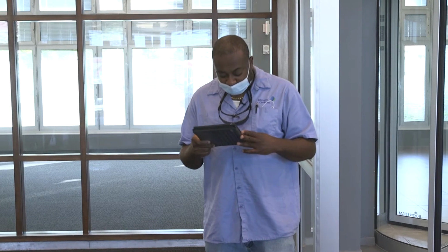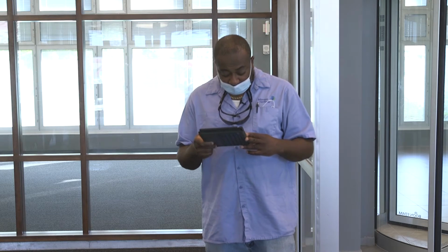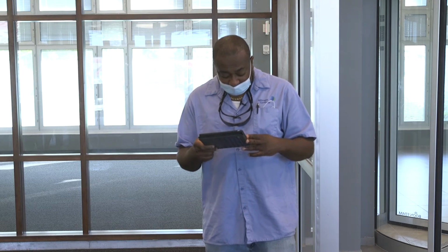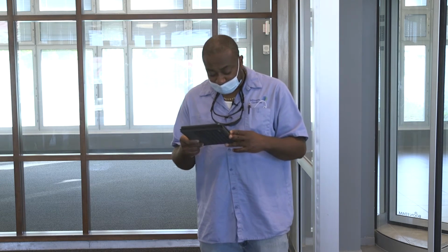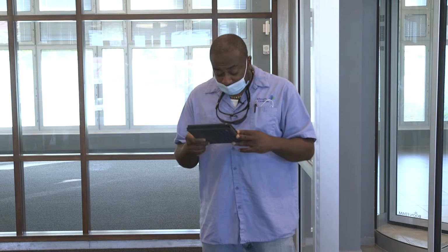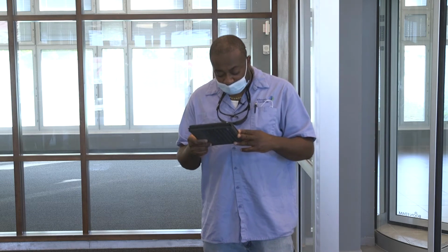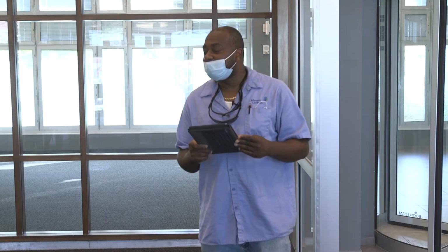The refrigerant systems are independently monitored and controlled. On any fault, only the associated system will be affected by any safety preventative action. The other refrigerant systems will continue to operate unless they are affected by the fault as well.